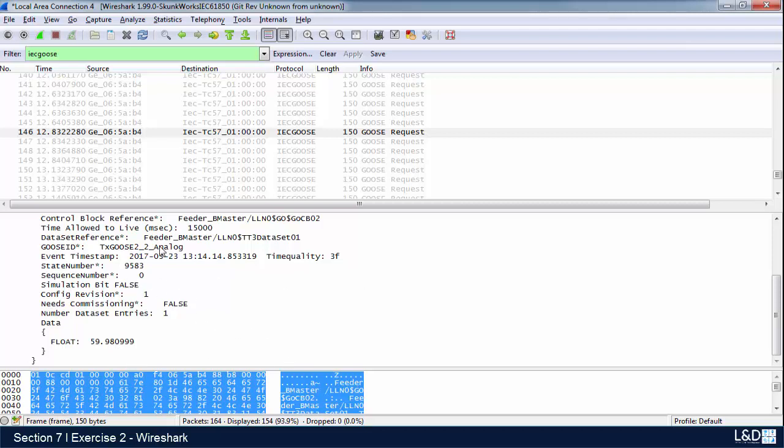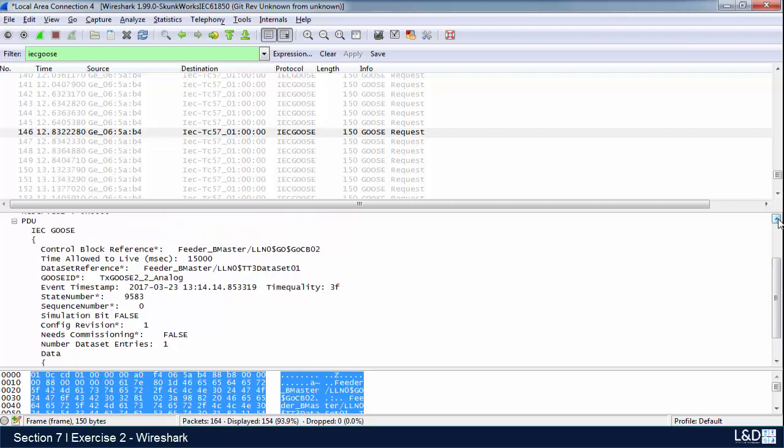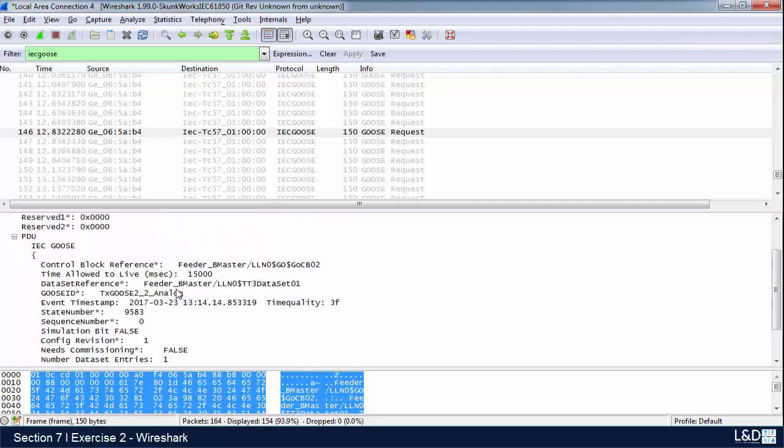That's being published out onto the network. Let's go through some of the things that are here on this screen. We can see that it's a GOOSE message. We can see what the references for the GOOSE control block are, the time allowed to live for the signal, this is our data set control block, the GOOSE ID, the date and time stamp when this was generated.